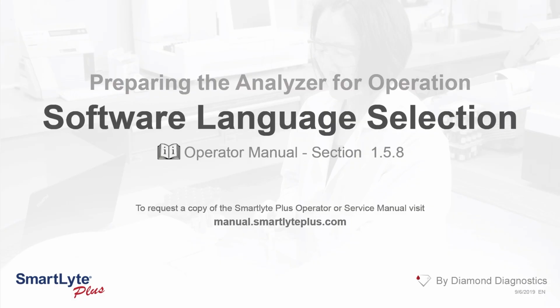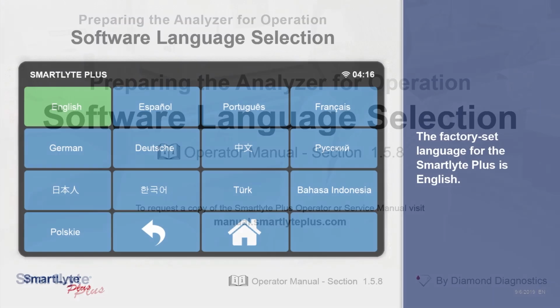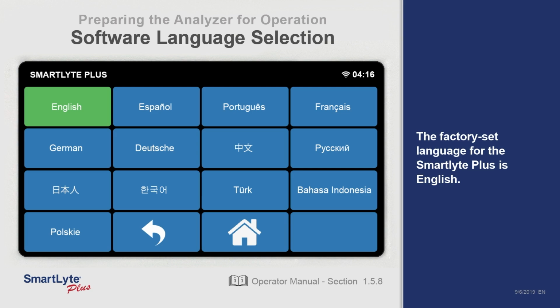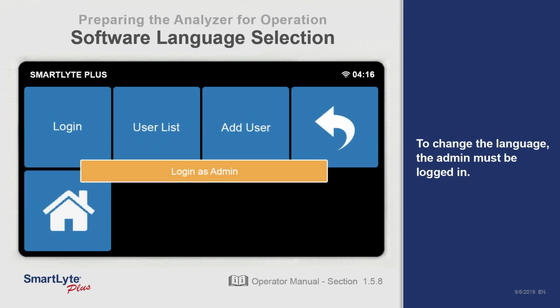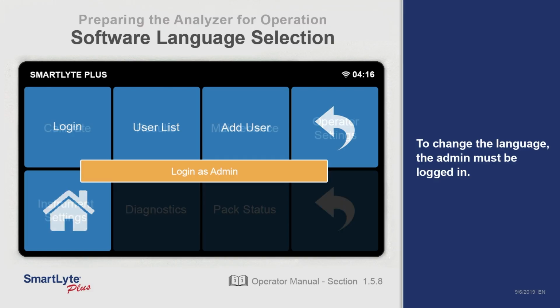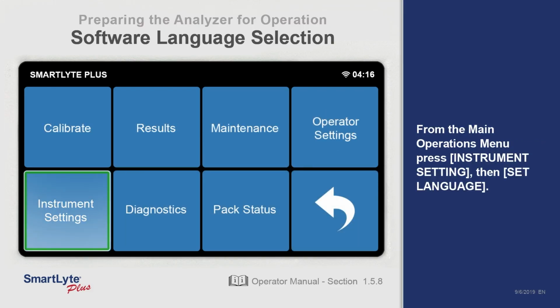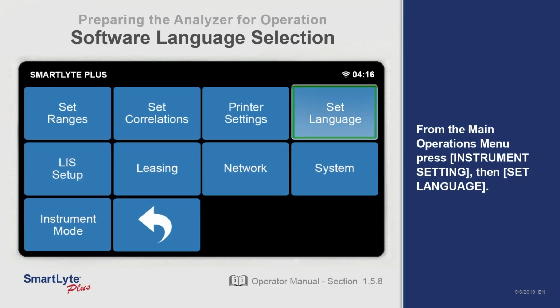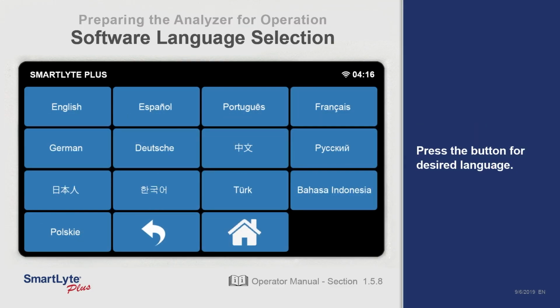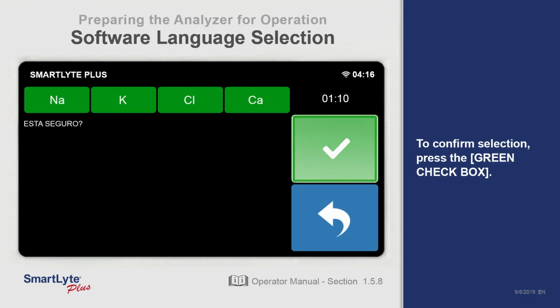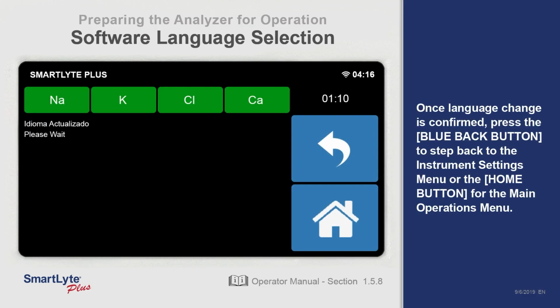Setting the language on the SmartLyte Plus. The factory set language for the SmartLyte Plus is English. To change the language, the admin must first log in. From the main Operations menu, press Instrument Settings, then Set Language. Press the button for desired language. To confirm selection, press the green checkbox. Once language change is confirmed, press the back button to step back to the Instrument Settings menu or the Home button for the main Operations menu.